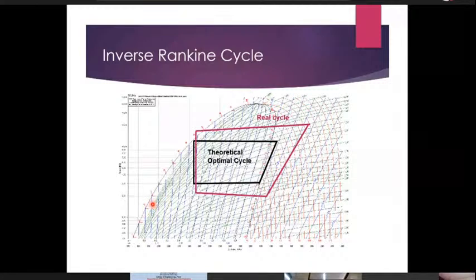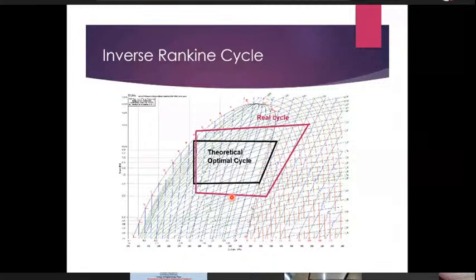Now, we would not want compression to happen in this region, because if we start ideally, the first step is that to have the highest coefficient of performance for any refrigeration system, we would look at operating at constant temperature. And the two-phase region of a refrigerant allows us that unique opportunity, that when we are rejecting heat at the saturation pressure, the temperature is constant, and the quality of refrigerant changes. So when it is absorbing heat, the quality would change from somewhere like 70% to 100% vapor. And if there was to be no pressure drop, then we would have the theoretical optimal cycle, which is the curve which is shown in black.